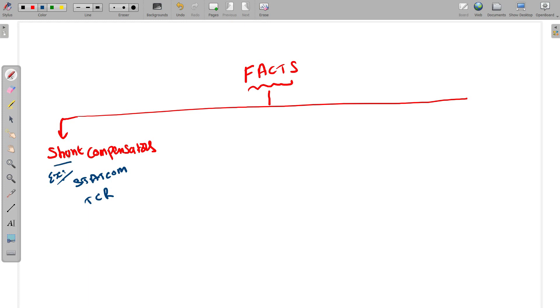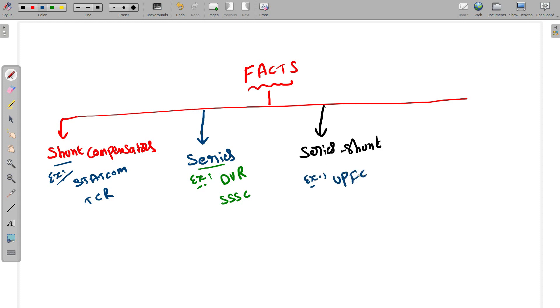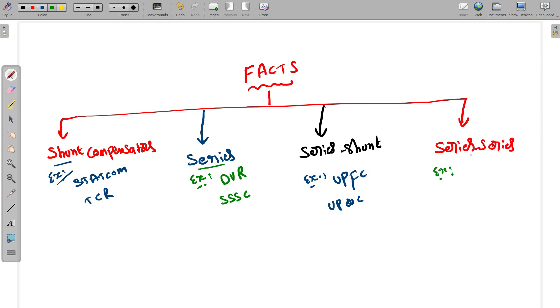The second category is series compensators — examples include the dynamic voltage restorer and the static synchronous series compensator. These devices are connected in series with the transmission line. The third category is series-shunt compensators, such as the UPFC (unified power flow controller) or UPQC (unified power quality controller), connected using both series and shunt configurations. The fourth category is series-series compensators, exemplified by the IPFC (interline power flow controller), connected between two lines in series.